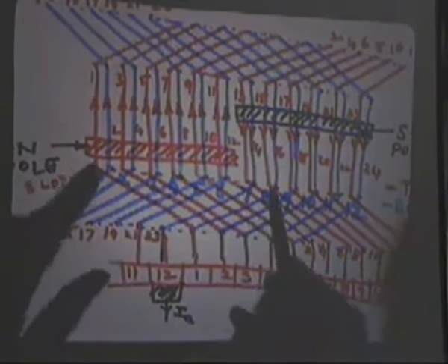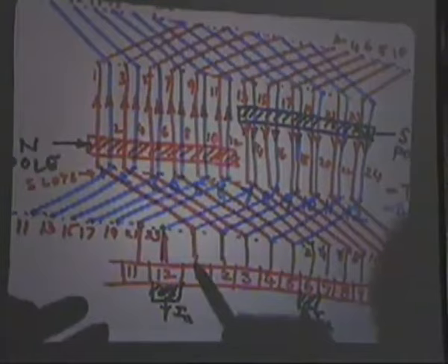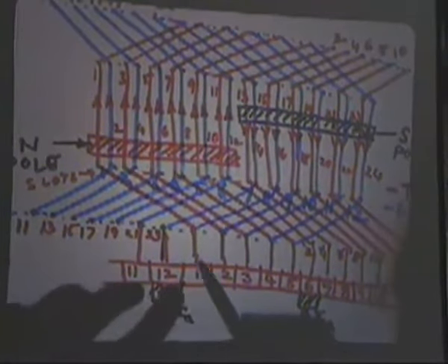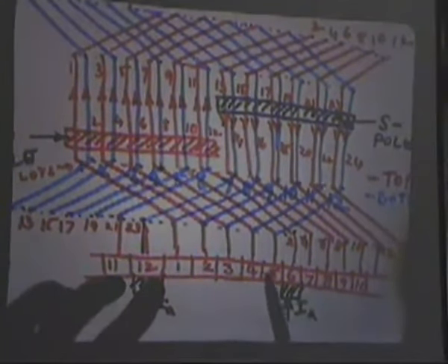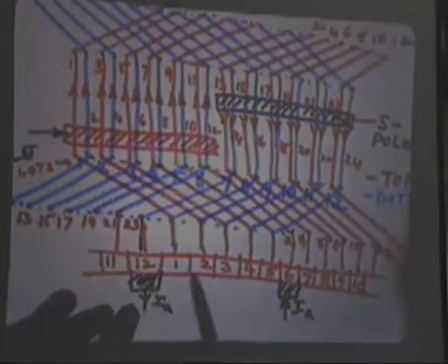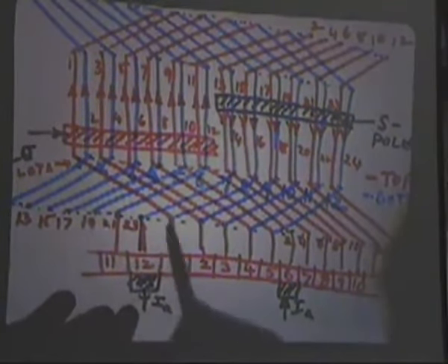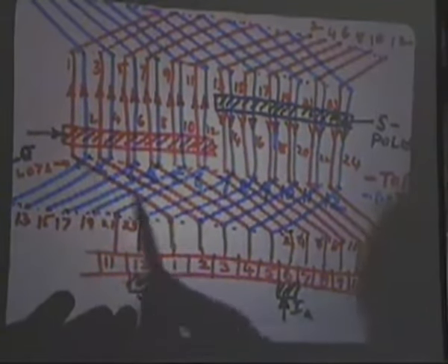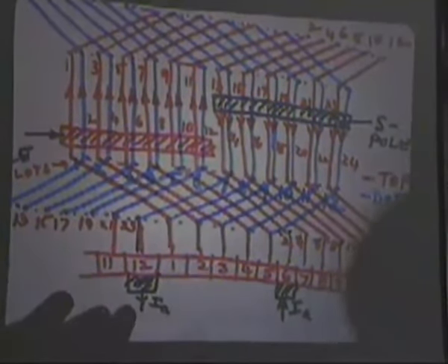So there is a 15 slot pitch, and that junction point is connected to commutator 1. Similarly, next junction to commutator 2, next to commutator 3, like this. So we will have 12 commutator segments, because there are 12 junctions here. But 2 of these coil sides will form one junction. There are 24 coil sides, so it will make 12 junctions, and that will be 12 commutator segments.